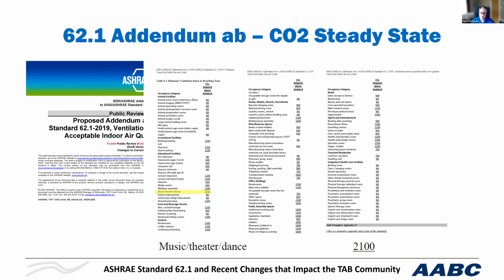And basically what the standard says is you should be ventilating for every occupant in the space. So the approach is you start to ventilate once the CO2 rises in the space. So if your outdoor CO2 is 400, and the CO2 is 450, 500, then you should start to be opening up the damper, and that's how the sequences should work. There are other standards out there that also say that it shouldn't operate until it reaches the steady state. Again, they're incorrect. Because the idea is we want to make sure that we always ventilate for the number of people there. And again, this is a lagging indicator. It's definitely not measuring the flow directly. And in some cases, it may make more sense to do direct counting.